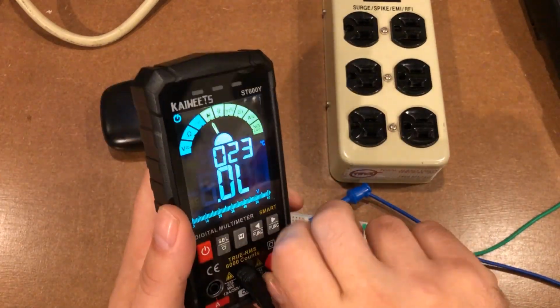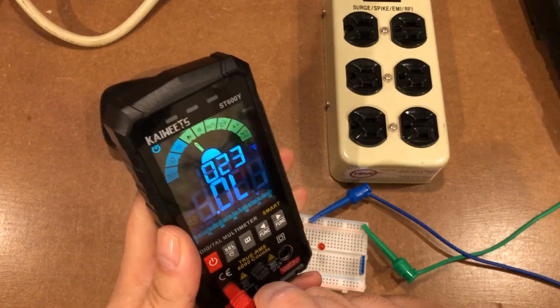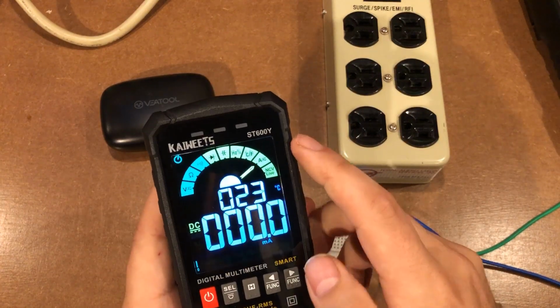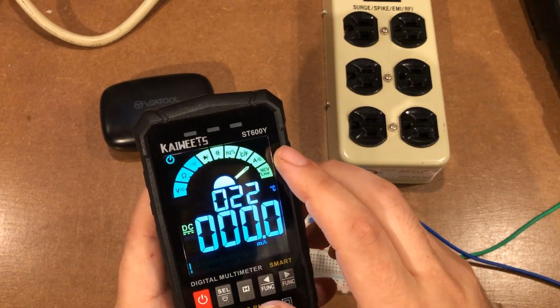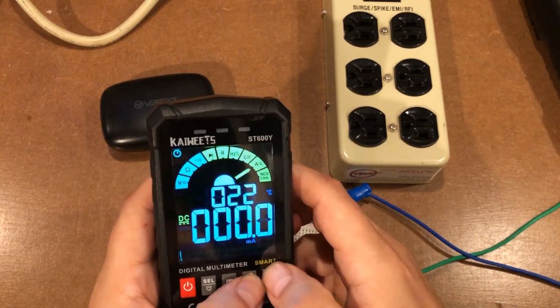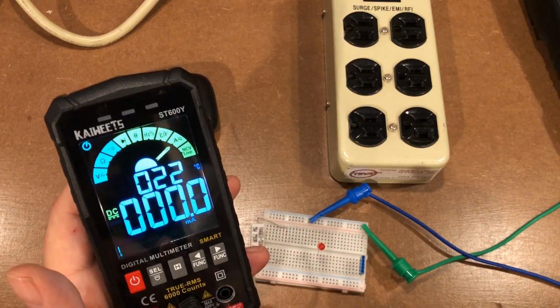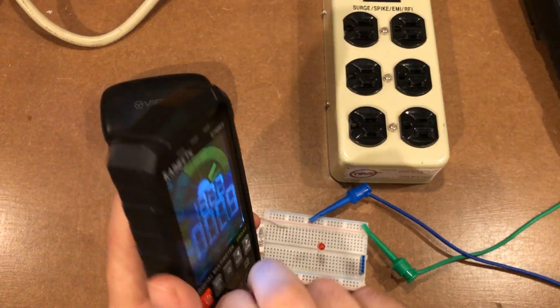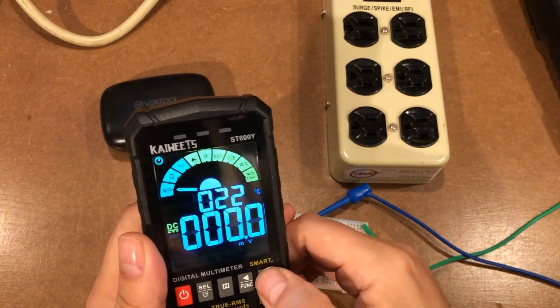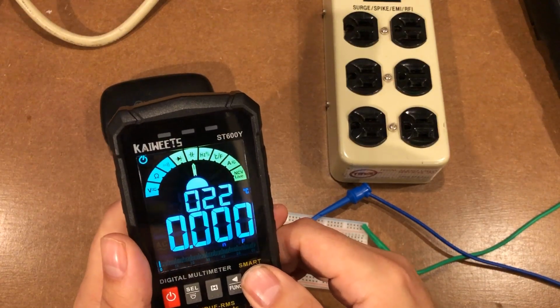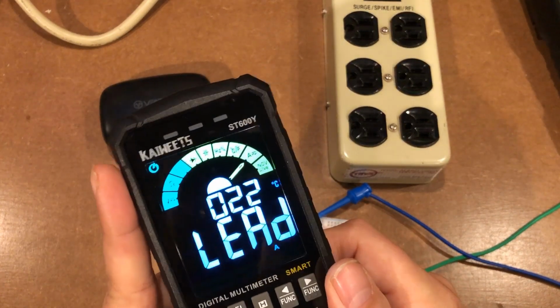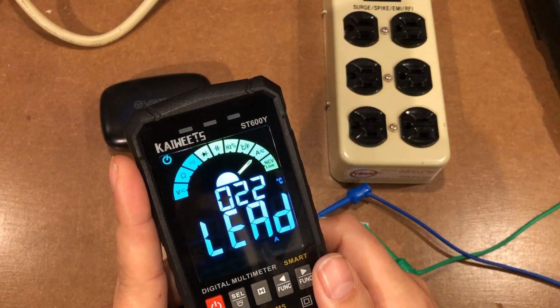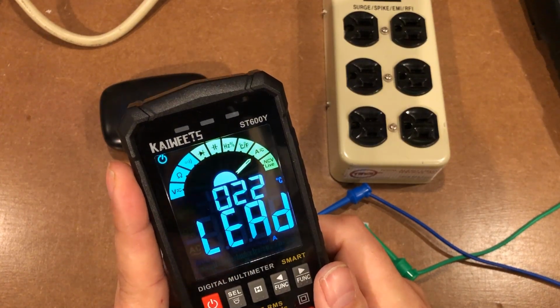What makes this one really interesting is that if you plug into the amps, it will automatically auto range over to the amp side. In fact, you can't get it out of that section, because that's the only way you should use this meter when the probes are in this position. And if you bring it back over and try to get into the amp section, it will tell you to move the leads, because it wouldn't actually do anything until you do. I think that is pretty dang smart.